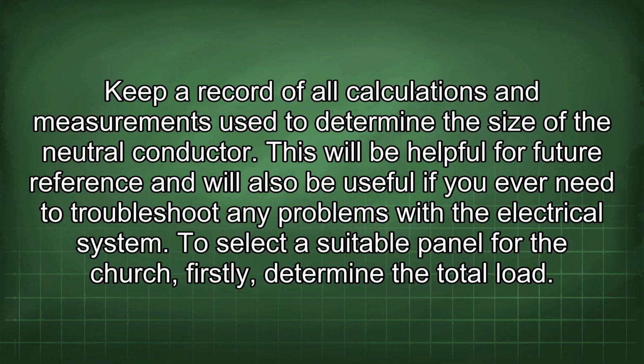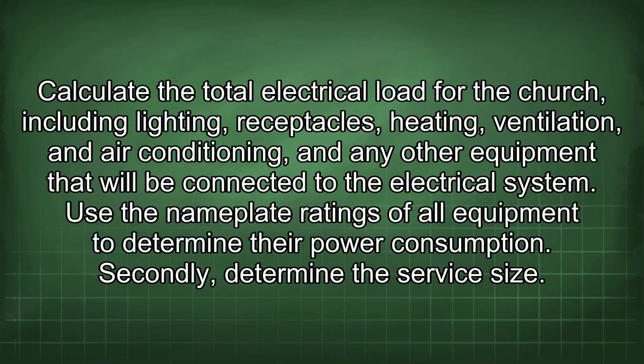To select a suitable panel for the church, firstly, determine the total load. Calculate the total electrical load for the church, including lighting, receptacles, heating, ventilation, and air conditioning, and any other equipment that will be connected to the electrical system. Use the nameplate ratings of all equipment to determine their power consumption.